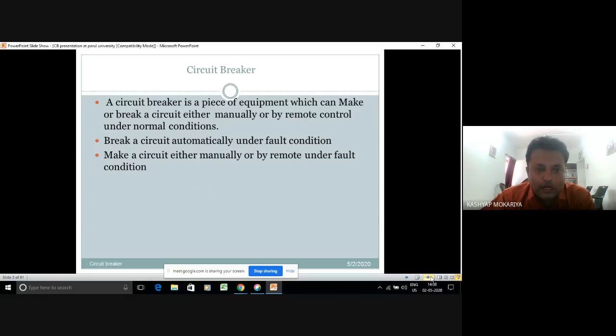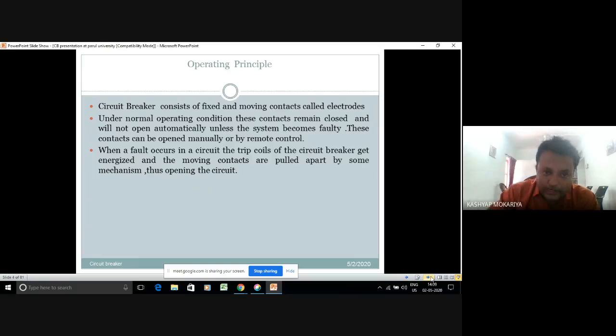So a breaker is a piece of equipment which can make or break a circuit either manually or by remote control under normal conditions, break a circuit automatically under fault condition, and make a circuit either manually or by remote control under the fault condition. It consists of fixed and moving contacts called electrodes. Under normal operating conditions, these contacts remain closed and will not open automatically unless the system becomes faulty. These contacts can be opened manually or by remote control.